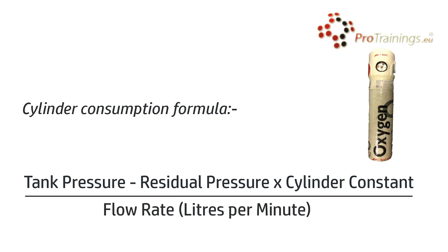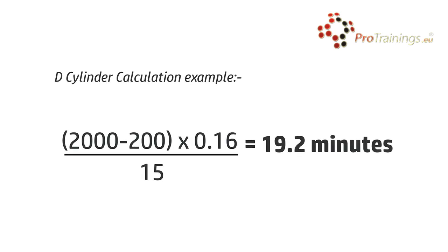Now let's calculate how long a D cylinder will last at 15 litres per minute. The formula is: tank pressure minus residual pressure, multiplied by the cylinder constant, divided by the flow rate — this gives the time in minutes. So: 2000 psi minus 200 psi equals 1800 psi. Multiply 1800 by the constant 0.16 to get 288. Divide 288 by 15 litres per minute to get 19.2 minutes, which rounds down to 19 minutes.